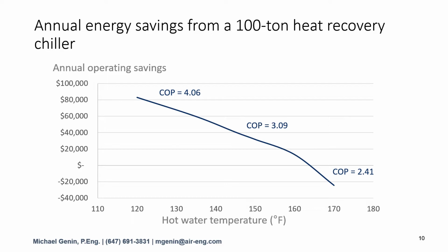However, you might have other factors to consider on a project such as greenhouse gas emissions, but certainly up to 160 degrees, heat recovery systems operate more effectively and have a lower operating cost when compared to conventional systems. This chart can be used as a quick guide to estimate the feasibility of a project. For example, a 200-ton system with 140 degree supply temperature would have an annual savings of about $100,000 per year, given that this graph is for 100-ton increments. We can then compare that to the expected capital cost of the project and quickly determine the feasibility of the project.